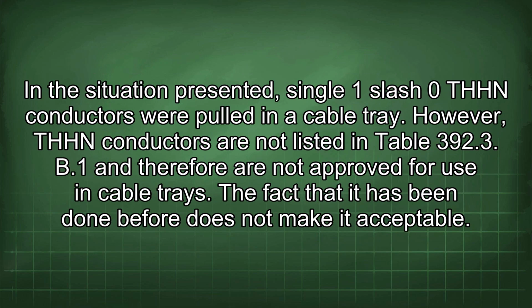In the situation presented, single 1/0 THHN conductors were pulled in a cable tray. However, THHN conductors are not listed in Table 392.3(B)(1) and therefore are not approved for use in cable trays. The fact that it has been done before does not make it acceptable.